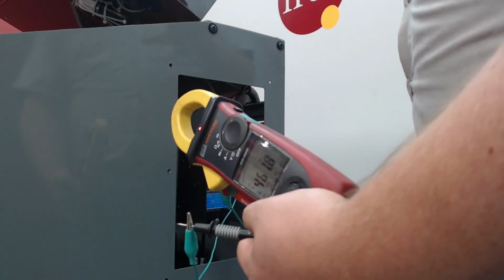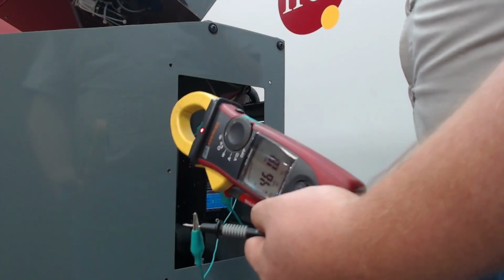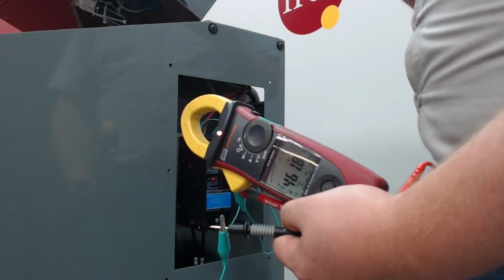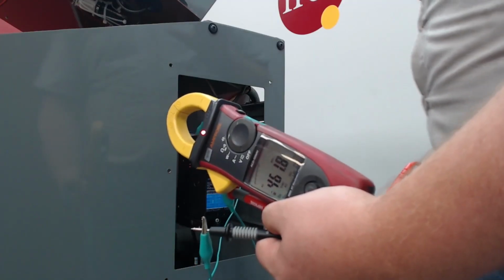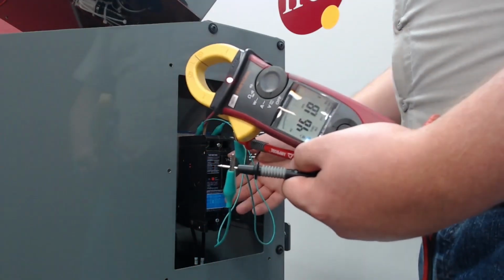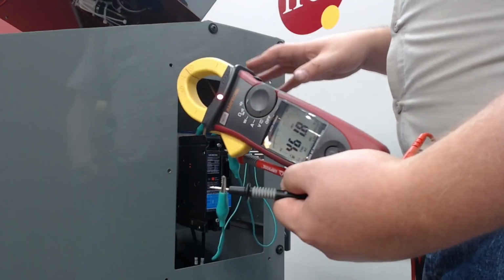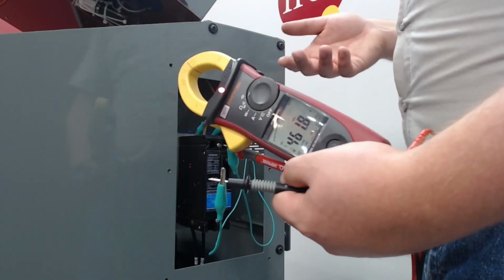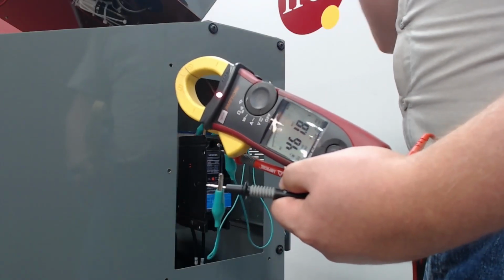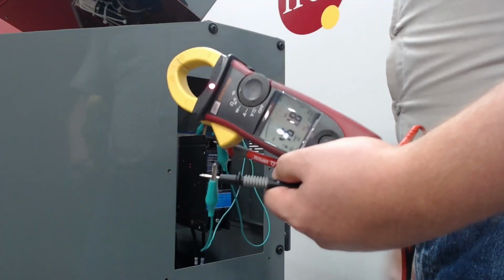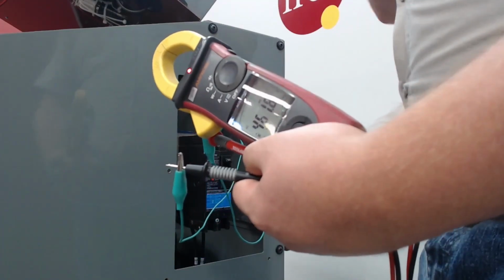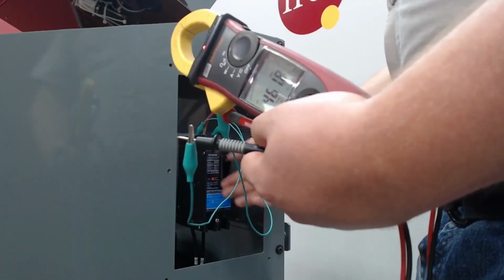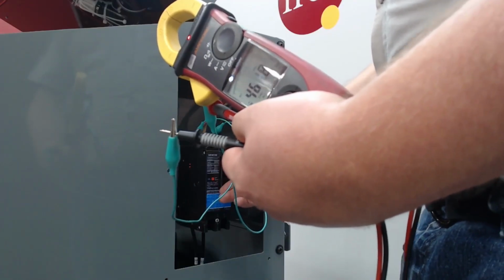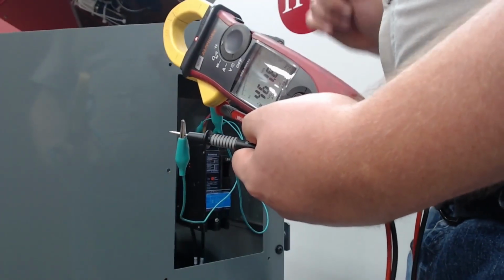This unit is designed to operate with as much power as it needs to operate, and if you don't have it, you're going to be getting into voltage drops. So that's where you check the incoming. You do that as many times as you need to before you can validate there is or there is not a voltage drop. I'll also show you how to be checking that on the currents up front. So I'm going to go ahead and turn the unit off for right now and disconnect my leads, and then we're going to transition over to the front of the unit.